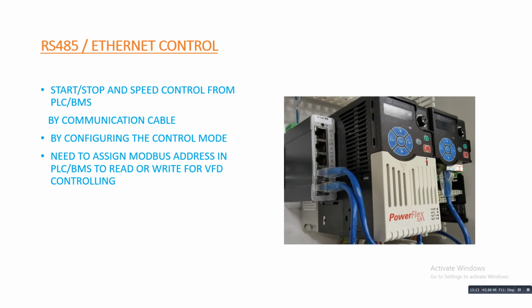For this case you have to configure this control method by selecting these settings in the VFDs. And also you have to find the Modbus address for the VFDs, and you have to assign it in the PLC or BMS. Then only this communication mode is possible.